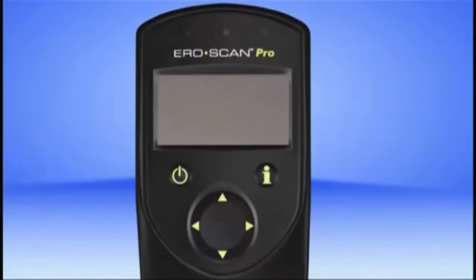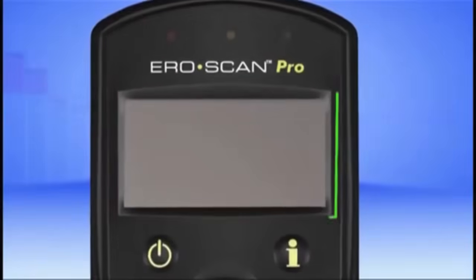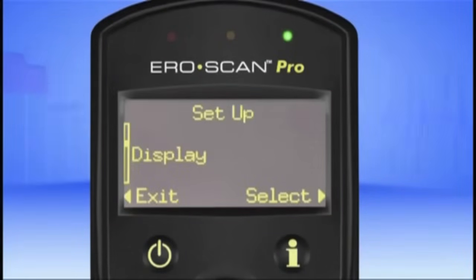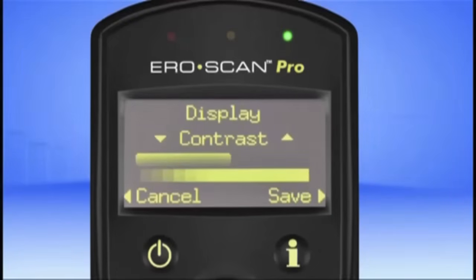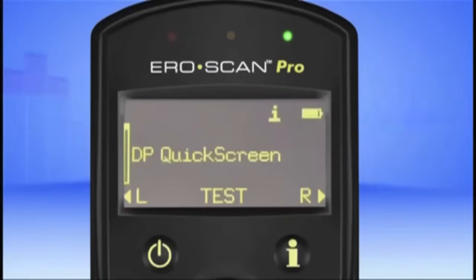Located on the face of the unit is the user interface or control panel. This panel contains all of the controls and status indicators used in the operation of your Ero Scan Pro. In the center of this control panel is the Ero Scan Pro's display screen. This display is your link to a wide range of valuable information, including everything from device setup parameters to test results. After powering up the Ero Scan Pro, we see the main menu displayed on screen. Shown on this screen are the battery level indicator, the additional information icon, and the main menu selection options.